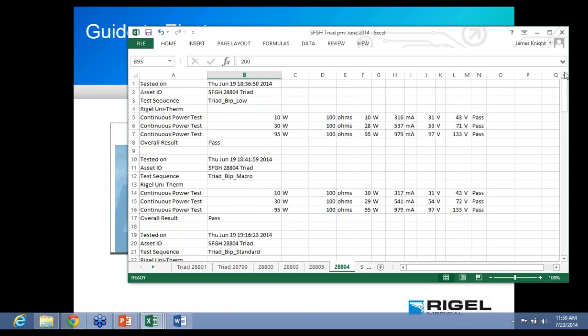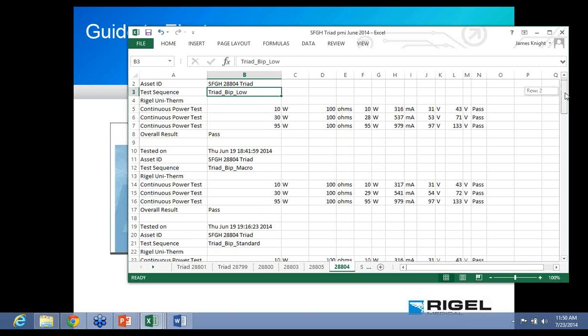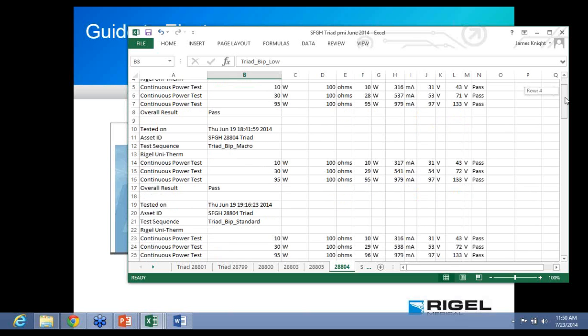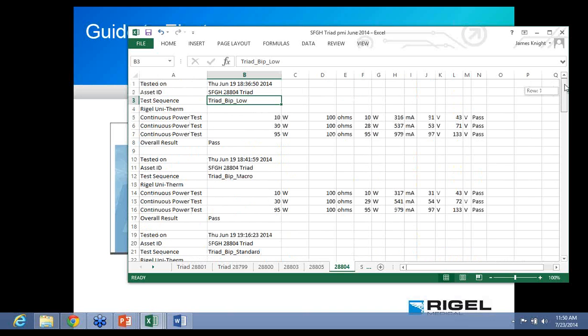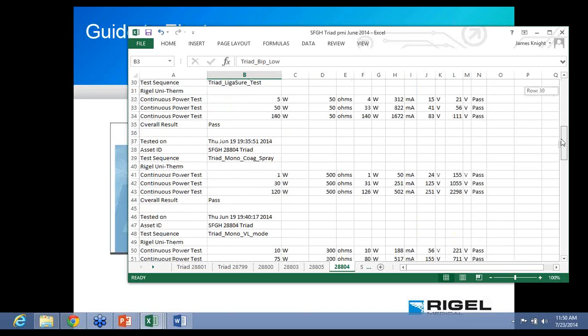I think I've got this down to 35 minutes. It was taking us 3 hours before. We're down to 35 minutes due to the sequencing. But this is the literal result. You know, the Unitherm actually tells you down to the seconds. This field right there, you enter it. This is the test sequence, and you've got to test the bipolar load in 3 different wattages. So you have to test 3 different loads and 3 different wattages.